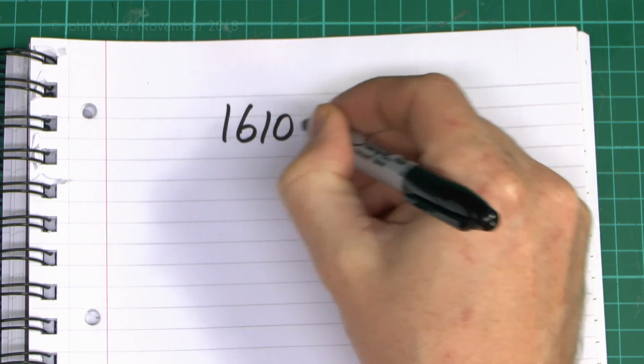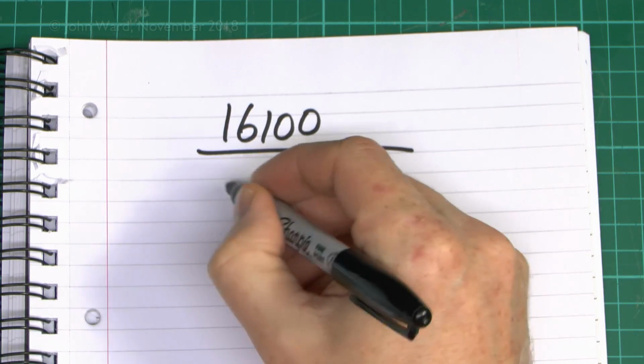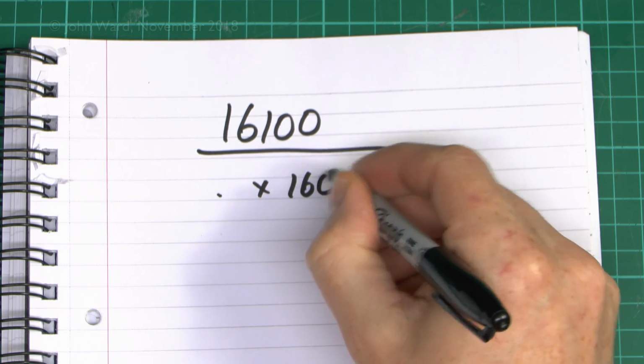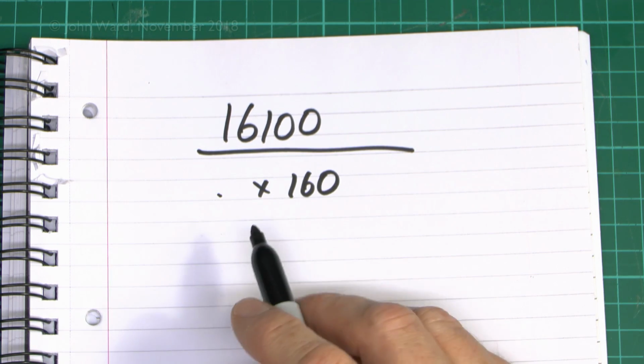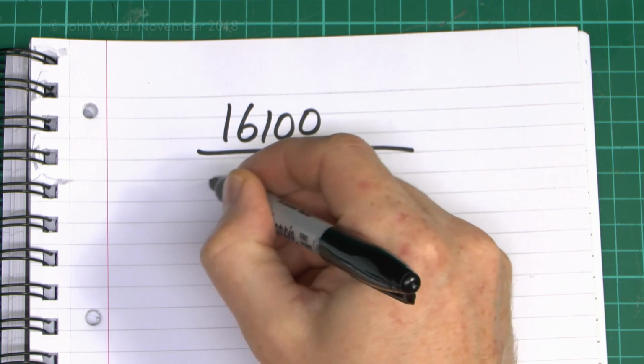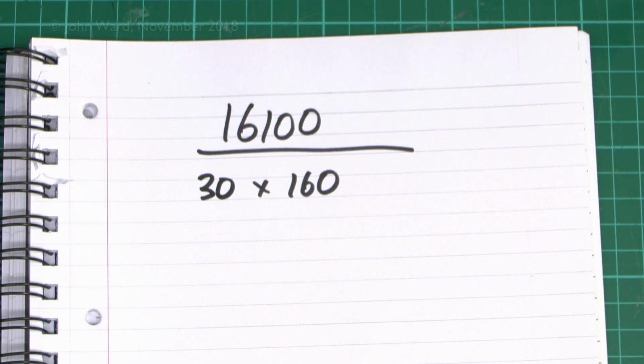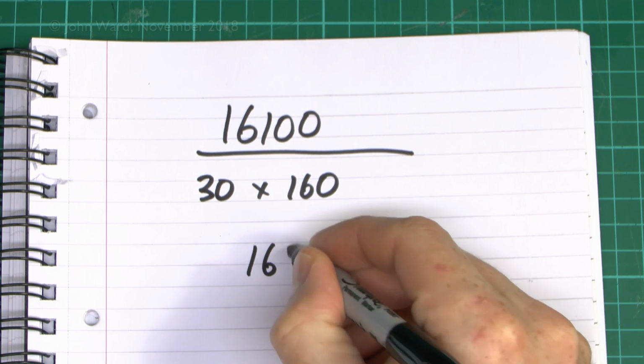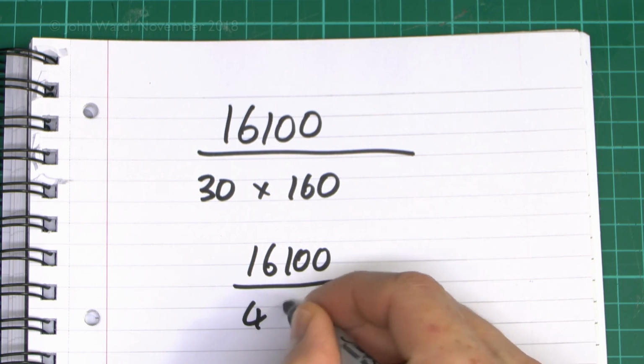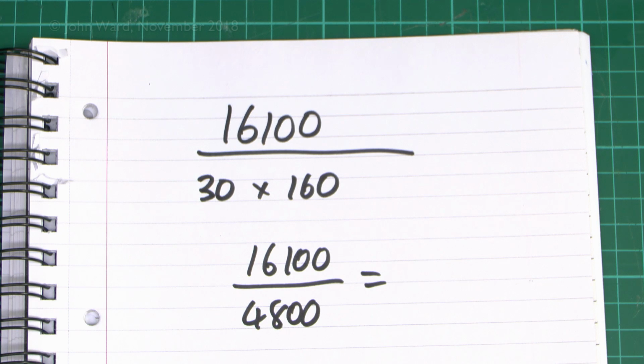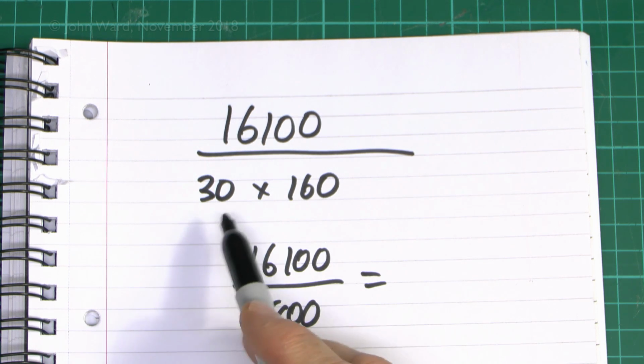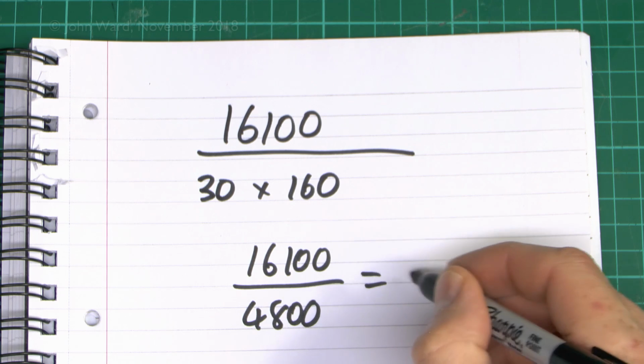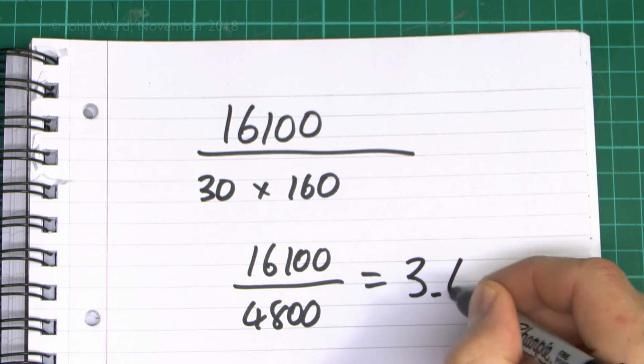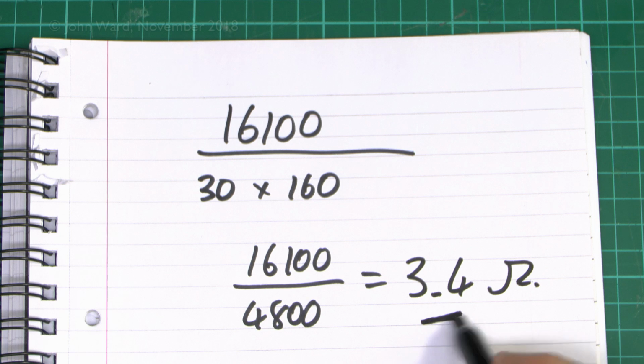Now let's just try that again. Let's use a different value this time. So we just have what we had on the previous page, which is the 16100 divided by the load times 160. Let's say the load was only the electric vehicle charging, and that would be simply in the region of say 30 amps to be a bit more generous. That gives us 16100 divided by 4800. So in this case, assuming we only go for the 30 amps of the actual vehicle, our maximum resistance for the electrode is 3.4 ohms. Again, a highly implausible and unlikely figure.